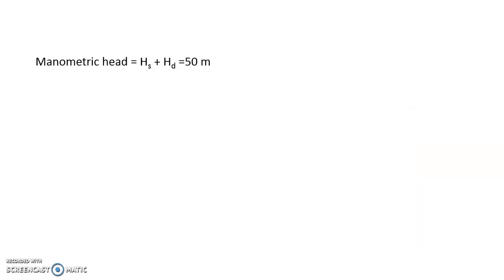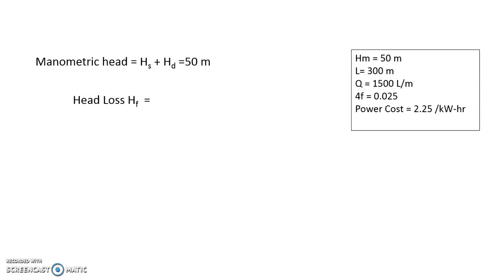So there is a manometric head which is suction head plus delivery head which is given as 50 meters but this is not the total head. For a given value of manometric head of 50 meters, length being 300 meters, discharge 1500 liters per minute - it's not in meter cube per second, we are supposed to convert it - and 4f. What is 4f? 4f is the friction factor where f is coefficient of friction. 4f being 0.025, we can apply the Darcy-Weisbach equation here to calculate head loss.